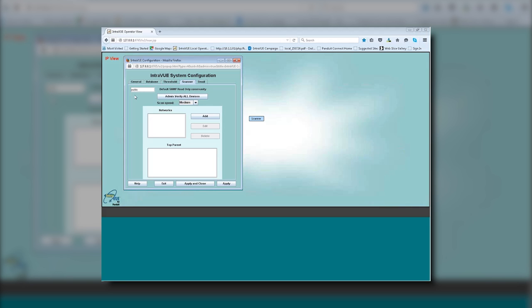Now, in SNMP, they have both read and read-write communities. The read-write allows us to communicate or write to a switch or an SNMP-enabled device. We do not require that. Matter of fact, we don't even try to use that. We want to be passive on our system. We don't want to provide information to individuals that could then go in and make changes. We are wanting only to get the information in a read-only way. And in most manufacturing locations, the read community will be different than the read-write, and it'll be very important, though, to get the read-only community.